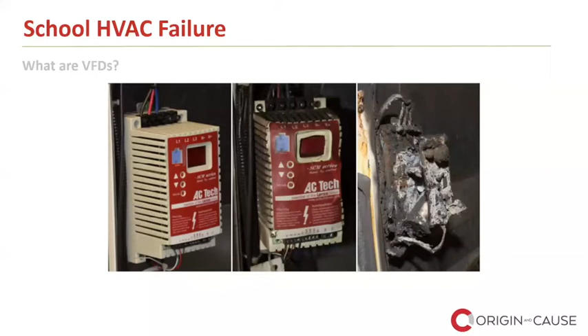And I do want to point out, yes, I am showing legible markings on these, but I don't want anyone to think that in this instance, the VFDs were defective. I'm not accusing this company of anything by any means. They were just exposed to input power that they can't cope with. Also, had the fault involved a defective unit, I would only expect one of them to fail rather than 2/3 of them.